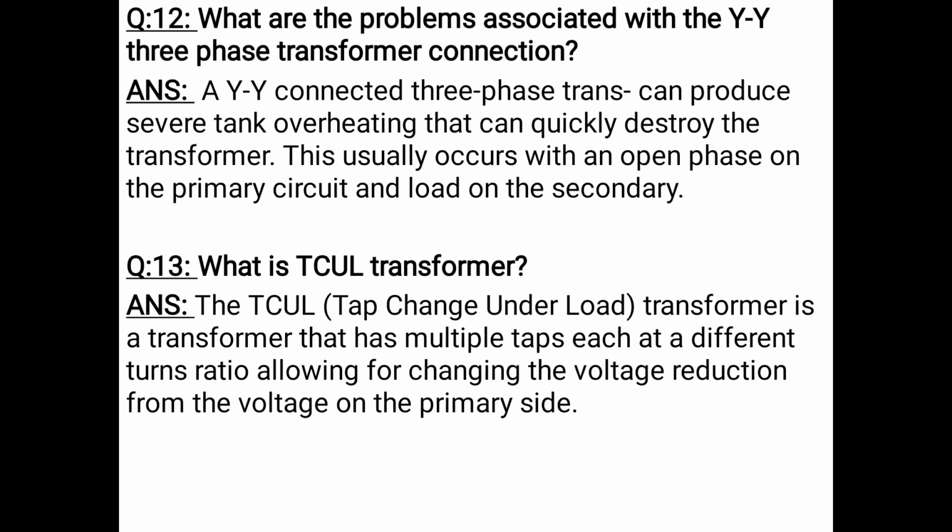Number 12. What are the problems associated with the YY three-phase transformer? Answer: YY connected three-phase transformers can produce tank overheating that can quite quickly destroy the transformer. This usually occurs with an open phase on the primary circuits and the load on the secondary.